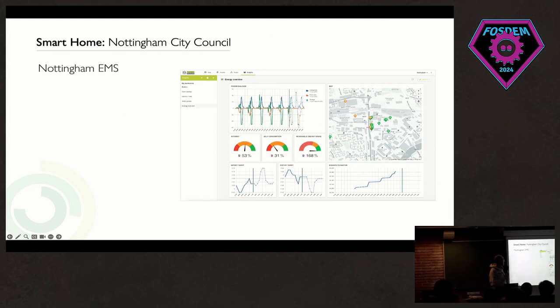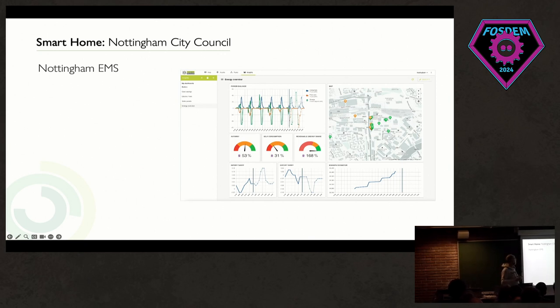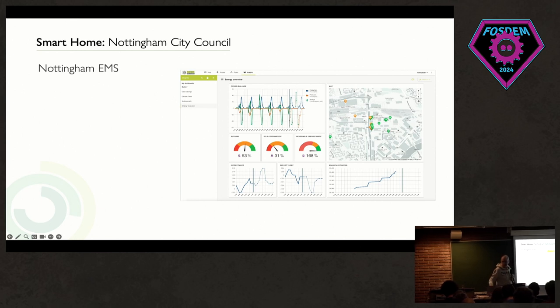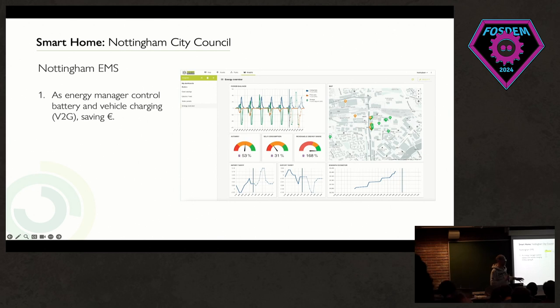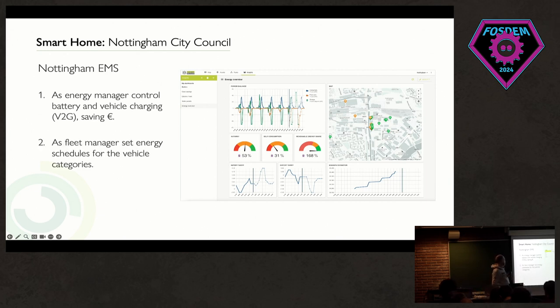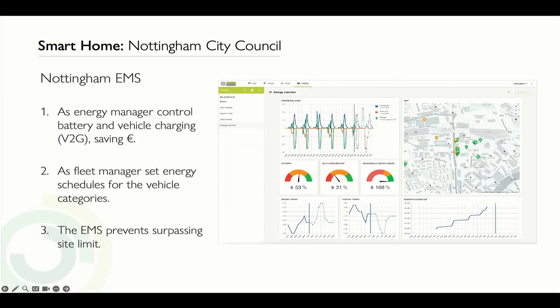One of the pilot projects is the Nottingham City Council. It's more like a smart office complex — the idea is to control the charging of all the electric vehicles used by the City Council in Nottingham. This means you can control a global static battery plus the charging of all vehicles to save money, ensure vehicles are charged to a minimum level because they need to be used, and prevent surpassing the power limit for the whole council. What you see on the right is the dashboard interface in Open Remote showing the different locations of the vehicles — tracked anonymously — and the global power currently used by charging those vehicles.